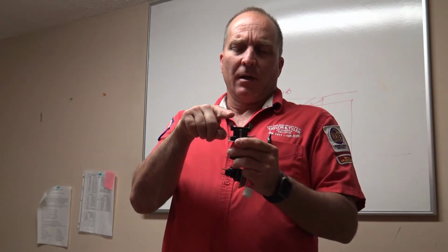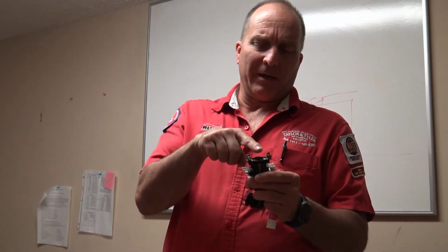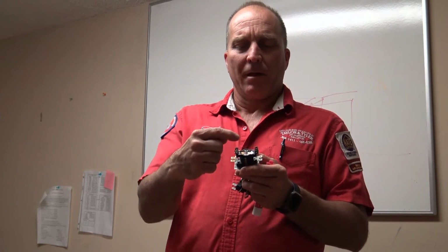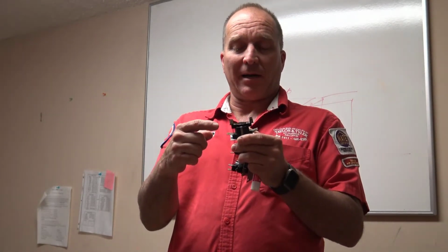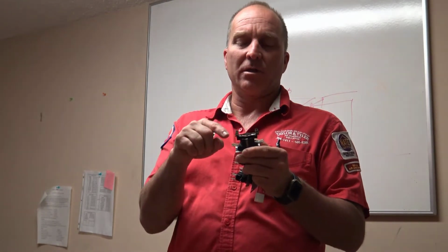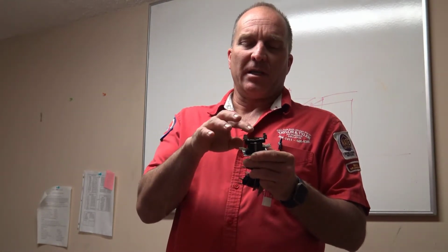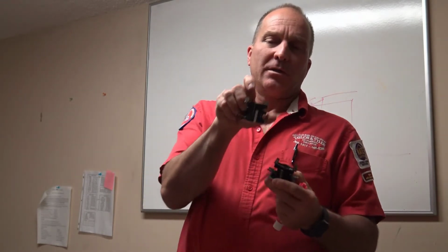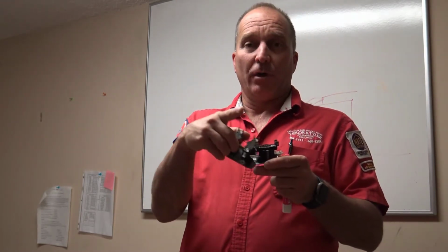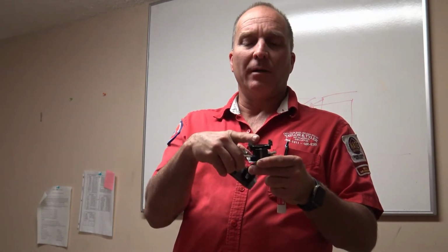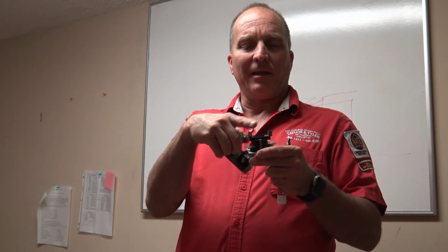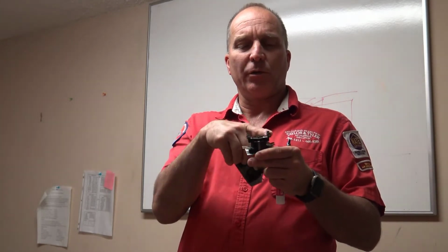This heat sequencer used to have another pole on top of it. This is one that literally comes from like a Goodman unit, and there was another pole on top of it that had one spade up on top of it. This is the only one that I've seen that is a normally open, normally closed heat sequencer. So if you see one with 3 poles as opposed to, say, 4 poles like this, that probably is a normally open, normally closed one. These two would be normally closed, and these two would be normally open. And then you use this as your common. And that would be normally closed, and that would be normally open. And you could use that as a fan relay with a normally open, normally closed switch.